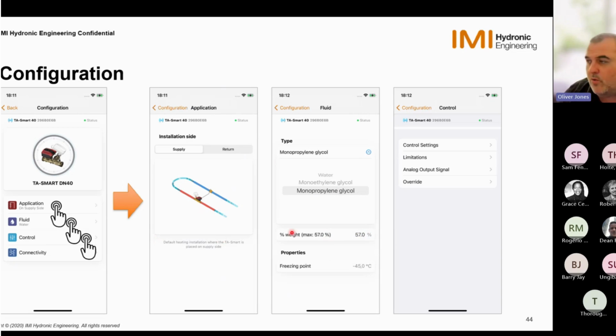And then if we click control, we go into our control settings. So we say here we want to control by flow or by power, what the limitations are. So what's our max flow, what's our minimum flow if it's not 0, because we can also set a minimum flow on 0 volts instead of fully closed. And our analog output signal if you actually physically want the output signal. And then there's overrides, which we'll cover on another day because there's more for showing how things work.